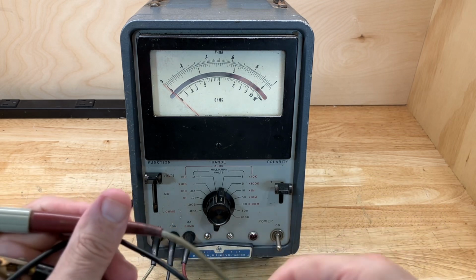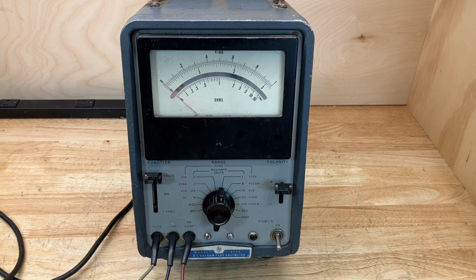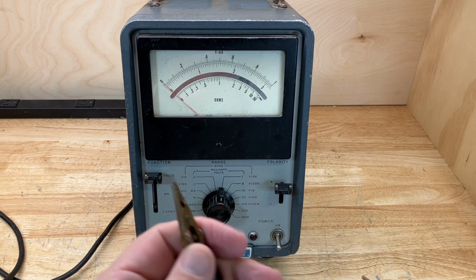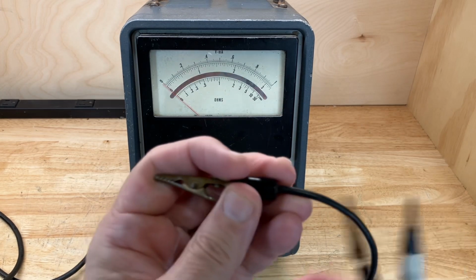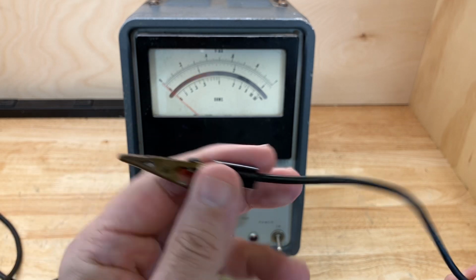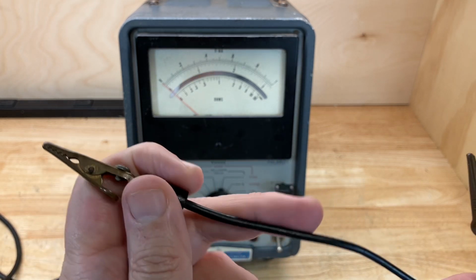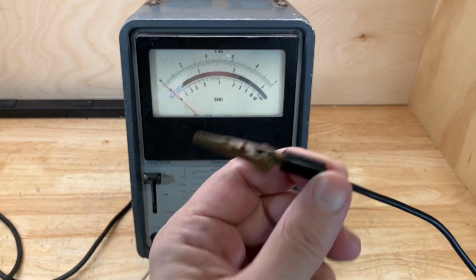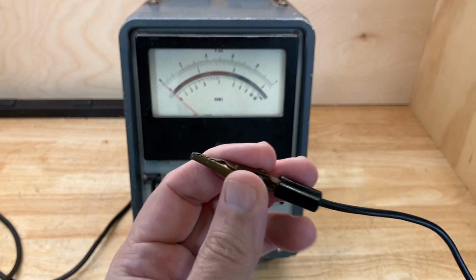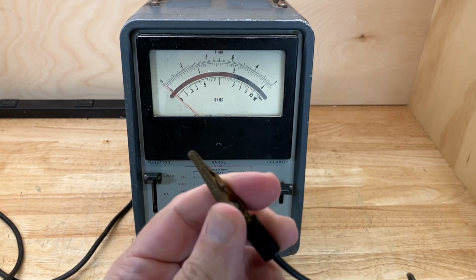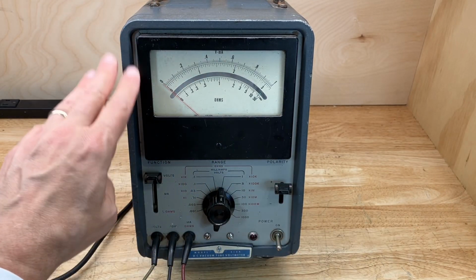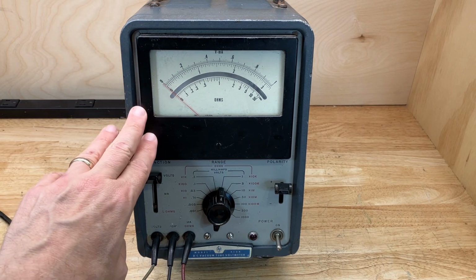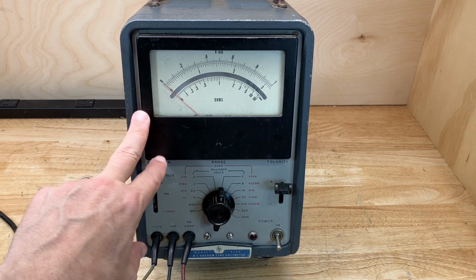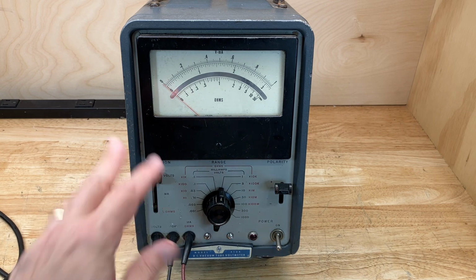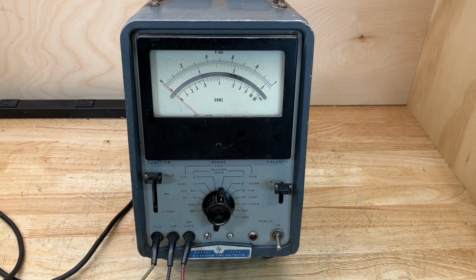This is a floating voltmeter. Unlike the AC voltmeters that I've been working on, this one, the low lead, the common lead, is not grounded. It's actually shielded by a grounded cable. The center of that shielded cable becomes the common low terminal connected to the alligator clip. So this voltmeter can make floating measurements up to 500 volts DC above or below ground. So this is a floating voltmeter, not like the AC voltmeters I've been working on.